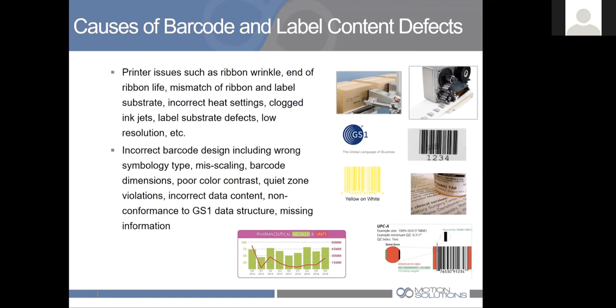Ribbon wrinkle is a potential cause in a thermal printer. In an inkjet system, you can have clogged inkjets. The label substrate may not be consistent. So the first roll or two of a print media maybe was fine, but then something happened with the supplier of that print media, and now you're getting some defects. So, a variety of things can happen throughout the production process that may cause issues. Labeling is one of the largest sources of recalls, both in medical device as well as pharmaceuticals. So it is a reality that there are issues around labeling that cause product recalls.